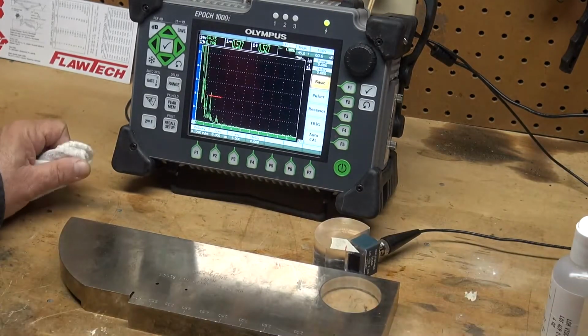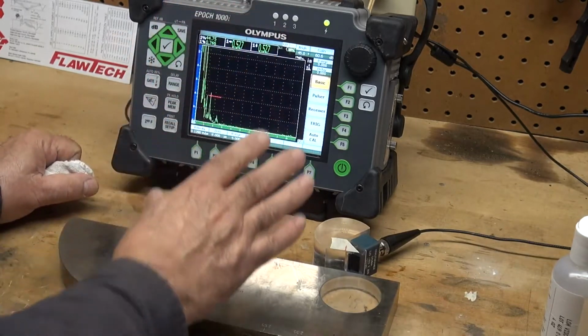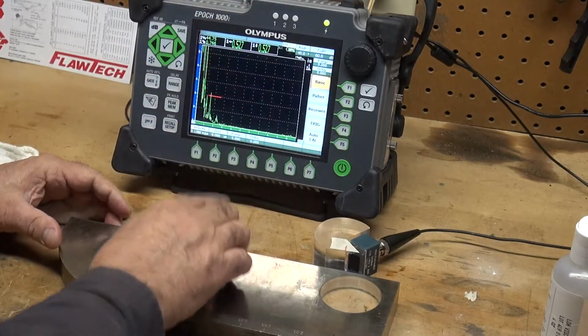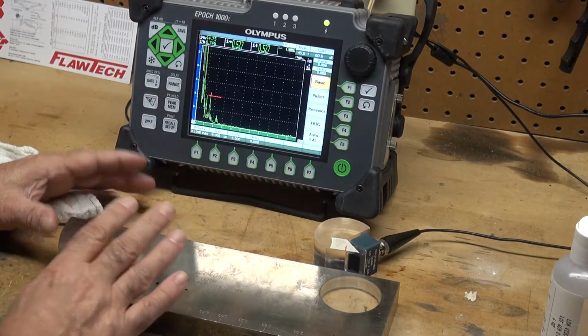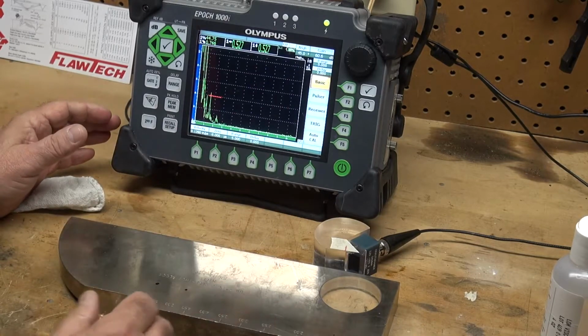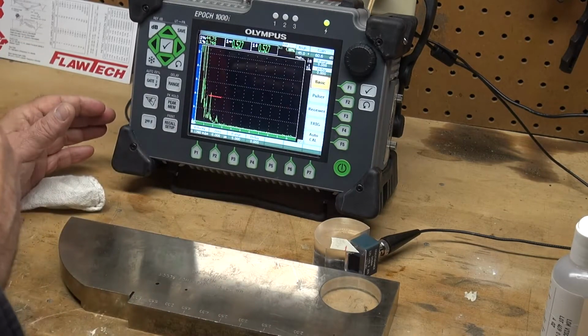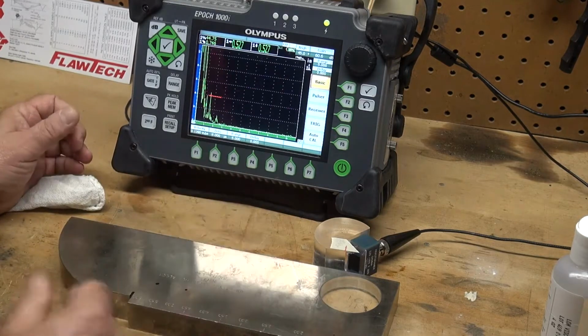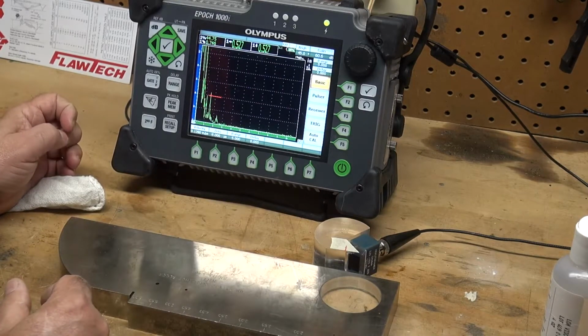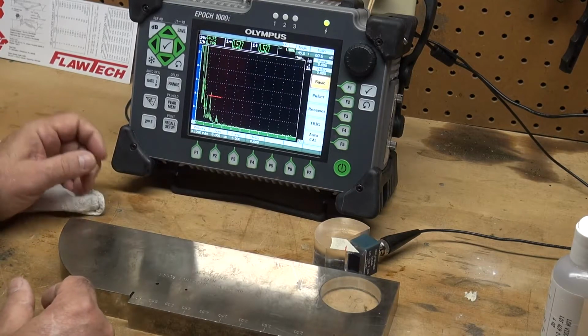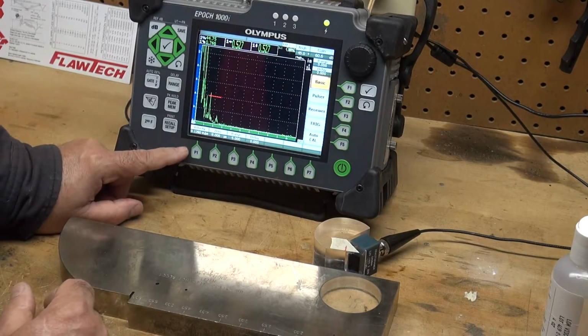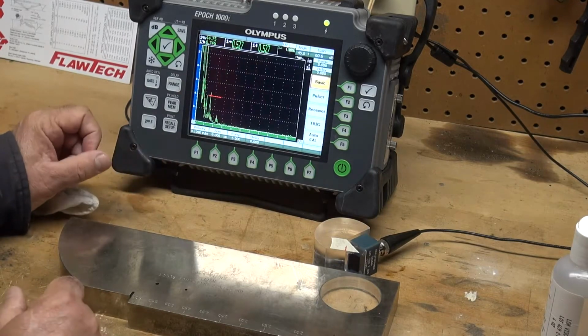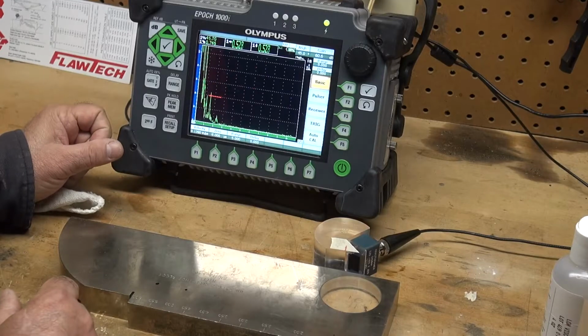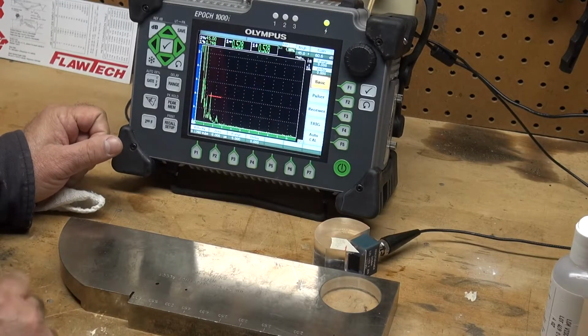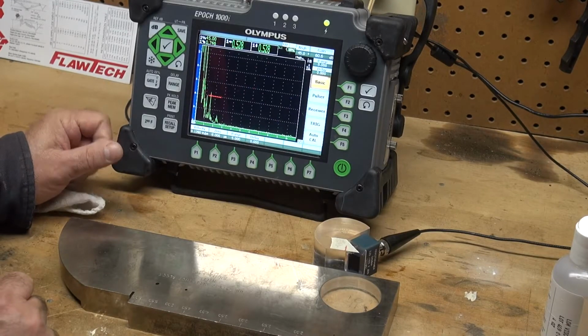So to start with, I set my machine range at 5 inches, because I'm using a 2 and a 4 inch radius. I want to set my range at 5 inches, that way I'll be able to capture both those reflectors, the 2 and 4 inch. My velocity is 0.128 inches per microsecond, which is your typical shear wave of mild carbon steel.